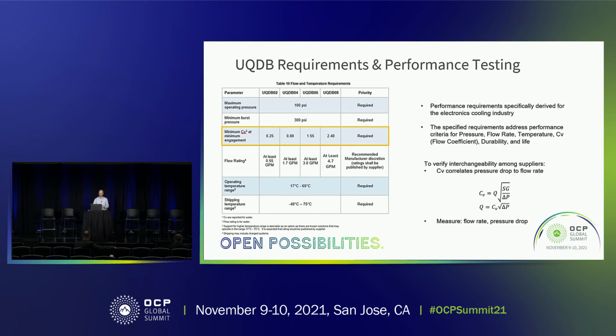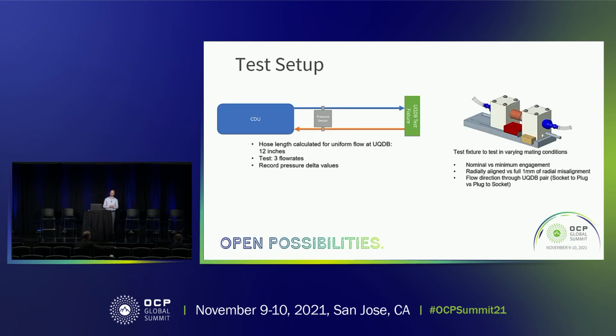So with that, getting into the test setup, you can see a simplified version of our test setup here, essentially using a CDU to push fluid past the differential pressure sensor through a certain length of hose that is calculated for uniform flow, and then ultimately through the test fixture and then the UQDBs themselves. Test at multiple flow rates to get that full pressure drop curve, recording the pressure or change in pressure values across the UQDBs at these different flow rates.